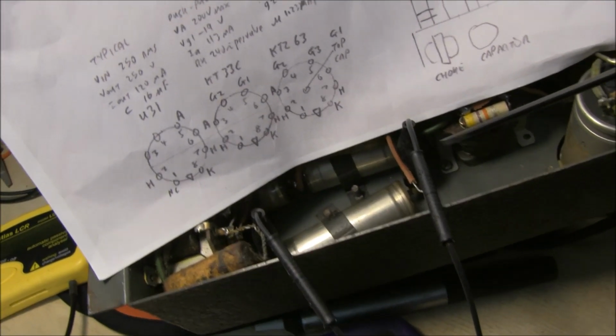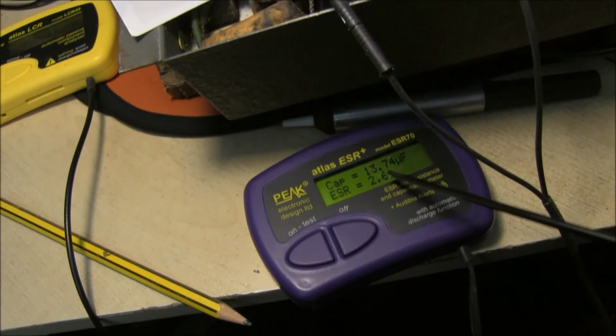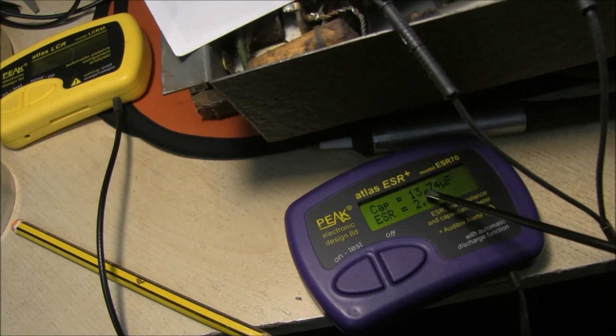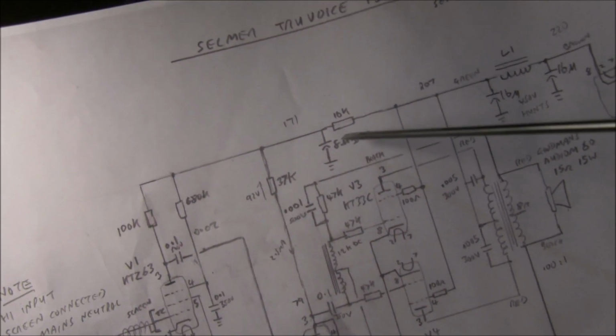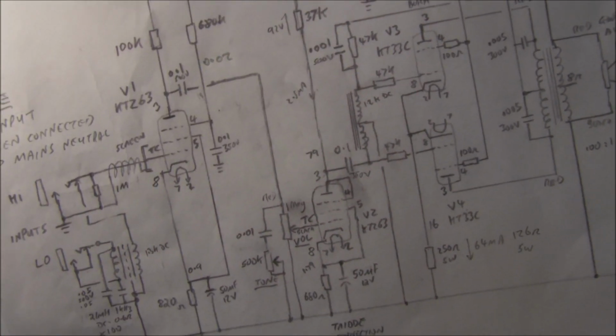So I've disconnected the end to get a reading. It says it's 2.6, which is not great, but 13, which is quite a lot higher than it was originally, means it's probably drying out. It's a fairly easy thing to replace. It's on a clamp, so I'm pretty sure I'm going to change that one.